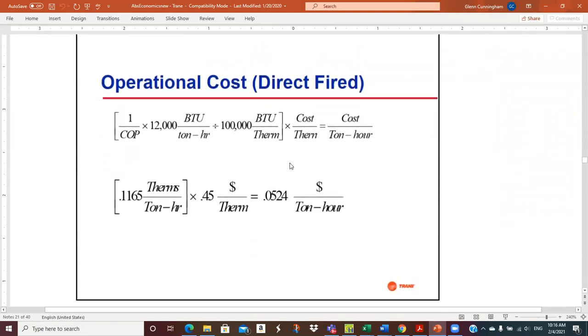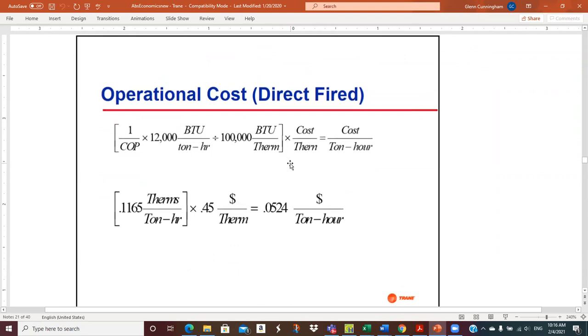Okay, so let's look at how they're going to calculate the operating cost. This is for the direct fired chiller. What we want to get is dollars per ton hour of refrigeration. And remember, a ton hour of refrigeration is 12,000 BTUs of refrigeration. If you look in this top bracket term, there's your 12,000 BTUs per ton hour. So that's the refrigeration. Well, the input energy we can get by dividing by the COP.